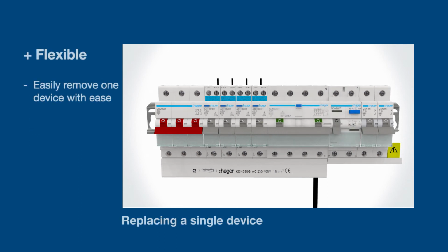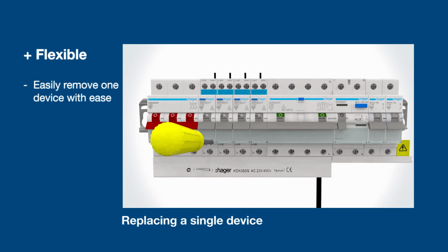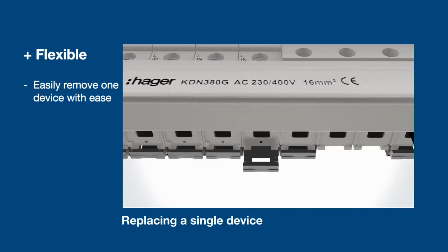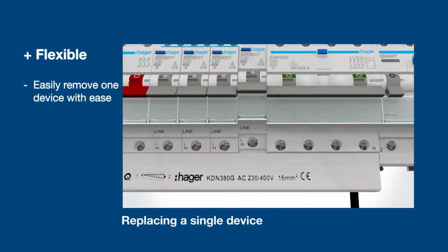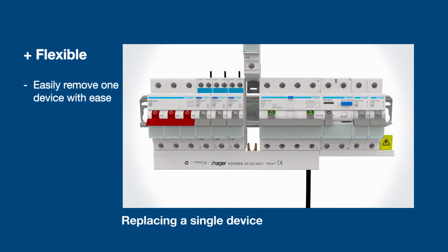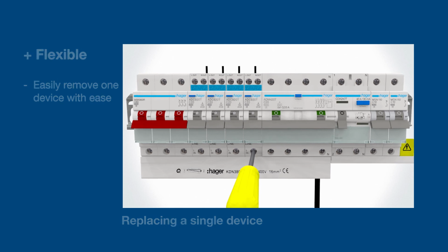This means that regardless of the devices you use, all are easily connected in the OneKonnect system. Removal of an individual device no longer requires removal of the busbar from all devices. Simply loosen the line-side terminal of the device to be changed, and with the hyper-extendable DIN clip fully extended, the device can be removed independently. Replacement of the protection device is just as simple as removal.